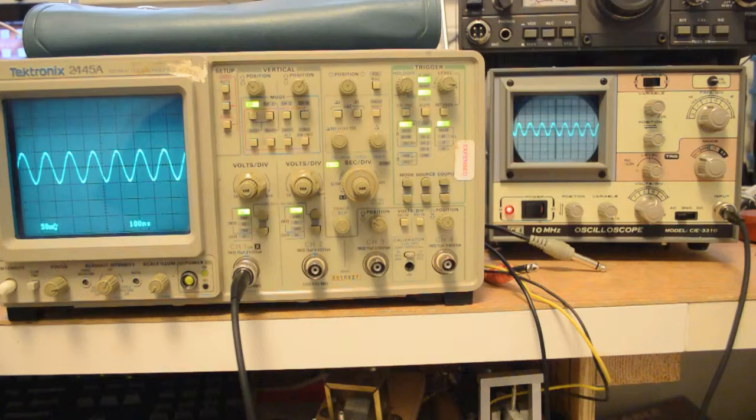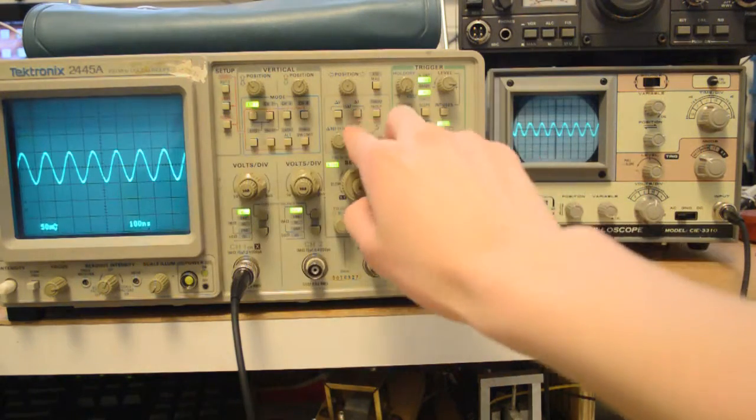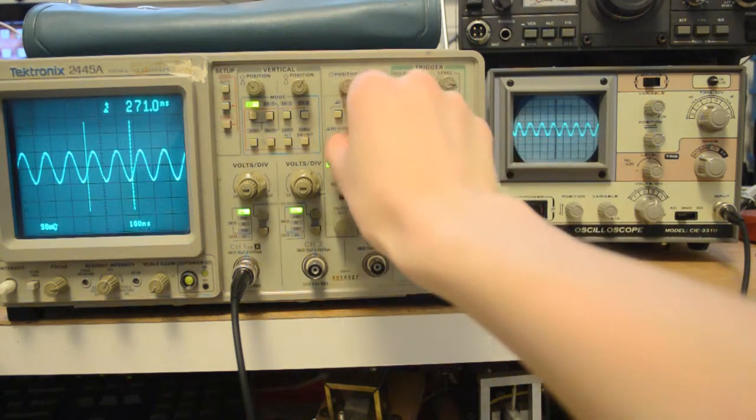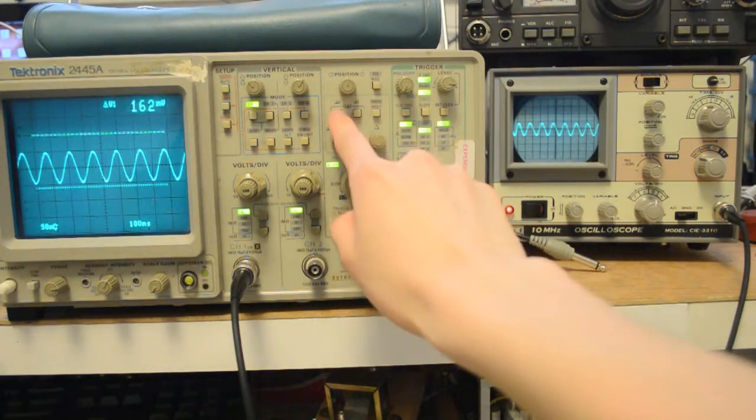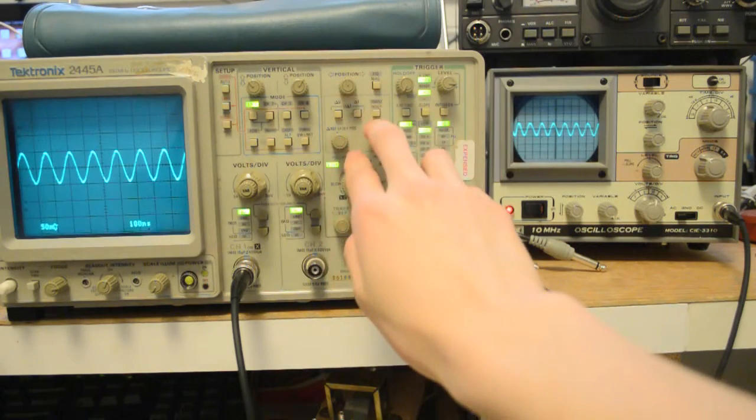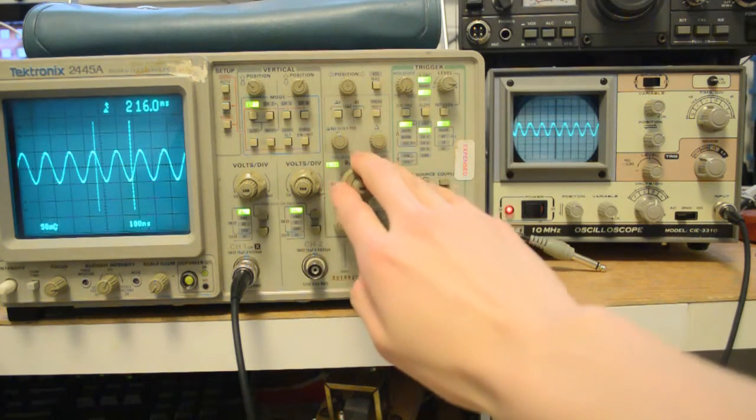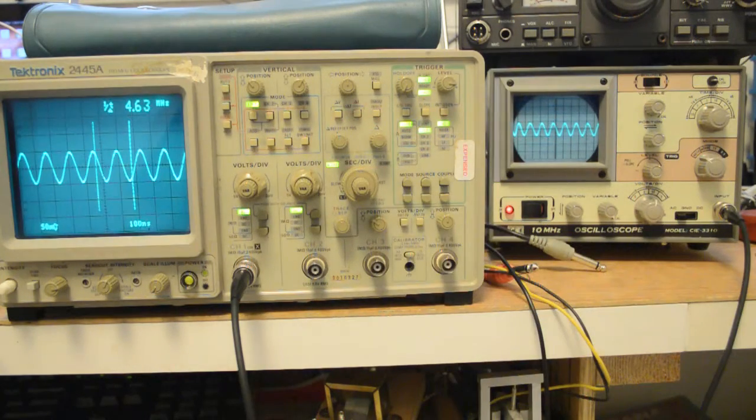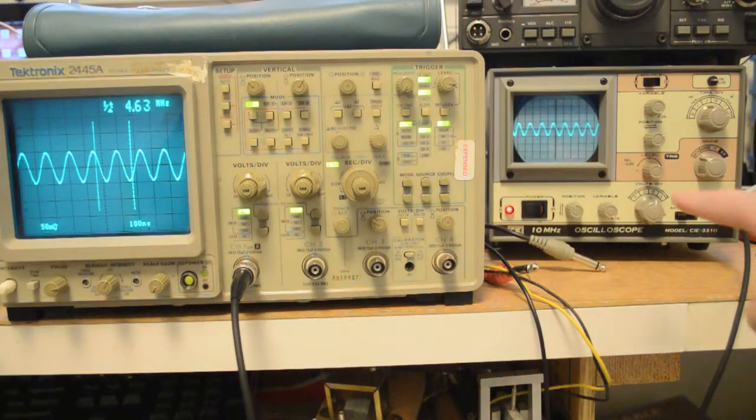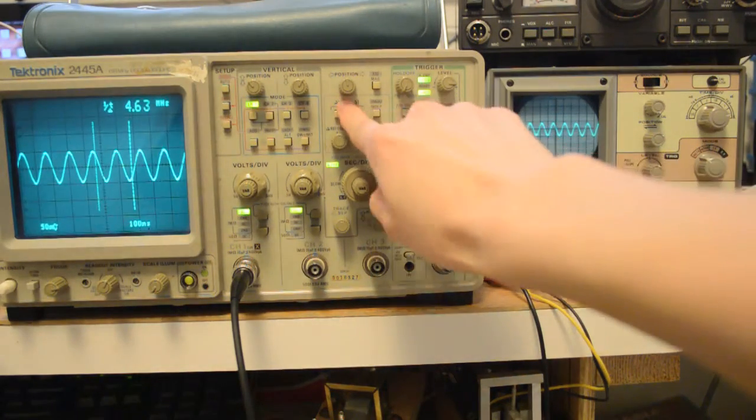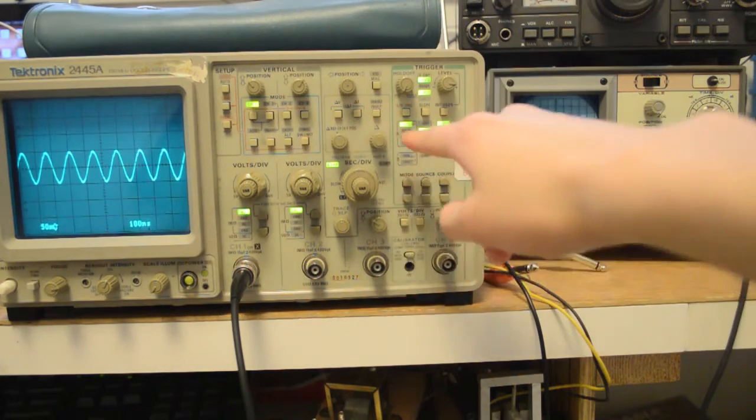And next, we have a ton of extra measuring options. So you can have delta Ts, and you can play with that. You have a delta V, and you can play with that. And you also have a... Press both at the same time. You also have a frequency measurement. There we go. This obviously has none of that fancy stuff. And then turn it off. Just press the button twice.